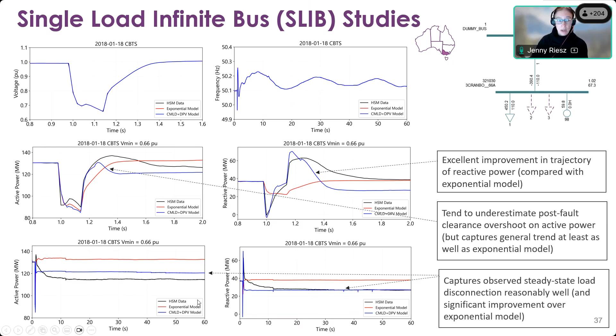One of the behaviors coming out of these models has been significant swings in demand that we're seeing post-fault. This first came up when we were using the models to study inertia requirements in the grid, and we noted there was this very brief transient increase in load immediately post-fault, which is due to the composite load model recovering slightly faster than the PV model post-contingency.